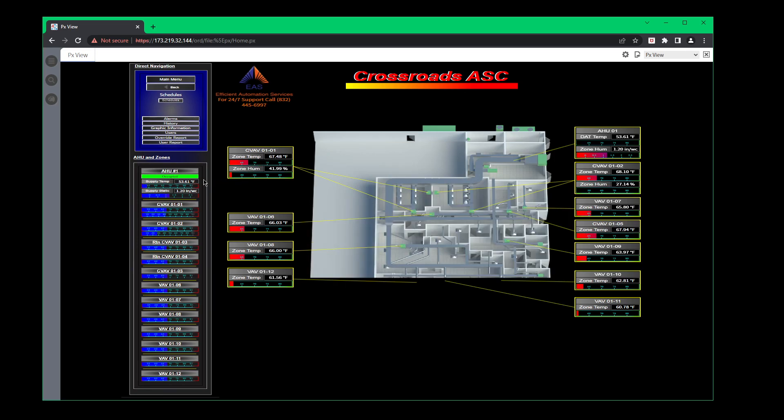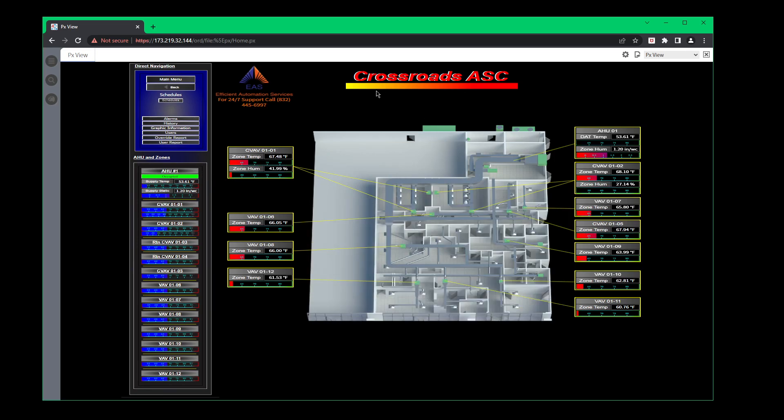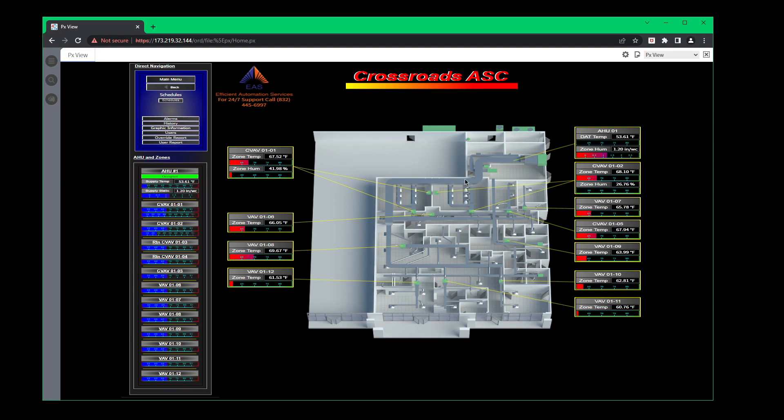Once you log in, you'll have the home page which is basically the layout for the building. It shows all the duct work coming off the air handler and going to its corresponding VAV boxes. Over here for the OR, you have constant volume boxes and a VAV box for the return. This box right here is always maintaining a certain flow into the space. If you want to go to a particular zone, you just click on one of these yellow boxes. Or you can do the same thing off the side tree right here off to the left.